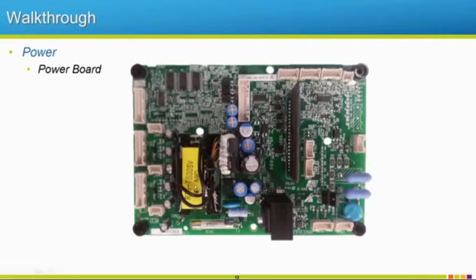And that's done through this transformer. It's just going to switch that high voltage to something usable to power that control board. So these vary depending on the drive size. Some of our micro drives actually have all of these boards and the main circuit soldered, sandwiched together. So some of those smaller drives are going to be, if you're trying to repair them yourself, are going to be not as useful to repair. But luckily they're pretty cheap, so you might as well just toss it and grab a new one anyways.